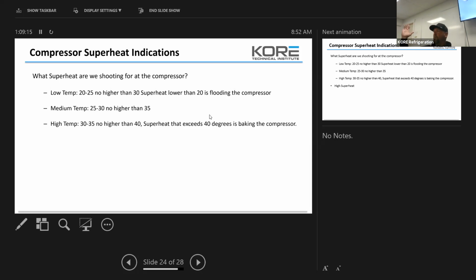If you guys are getting over 40, and this is not for HVAC compressors. You guys have heard of high temp and low temp application compressors. The reason there are different applications is because there are different components. The windings are coated differently. The metals are different in the reeds and such. High temp compressors, AC compressors, are meant to handle a lot more superheat. That's why, when you buy compressors, your invoice says low temp, medium temp, high temp. It's because they're not all built equally. They're built to the application.